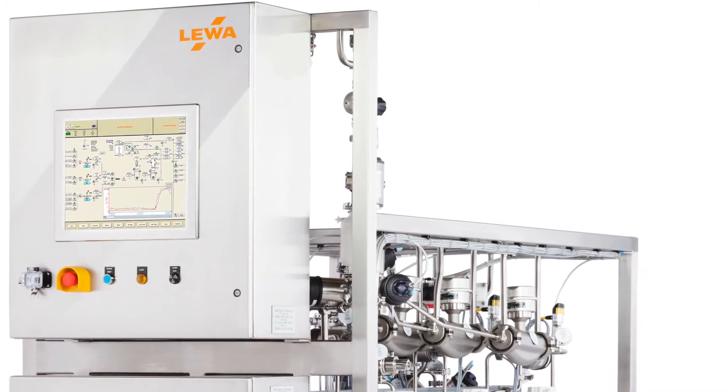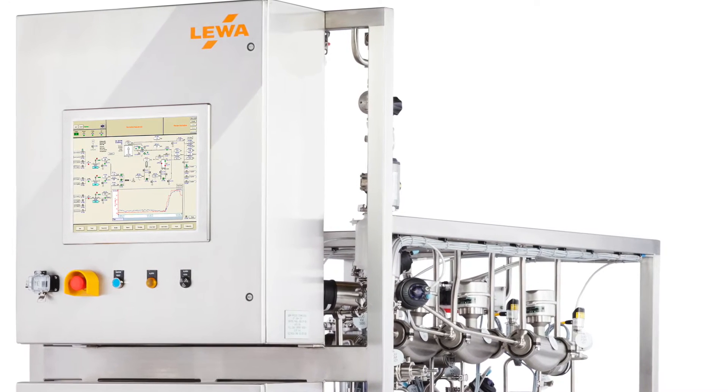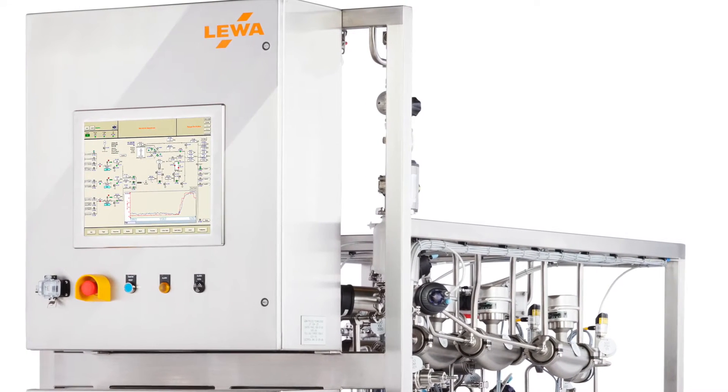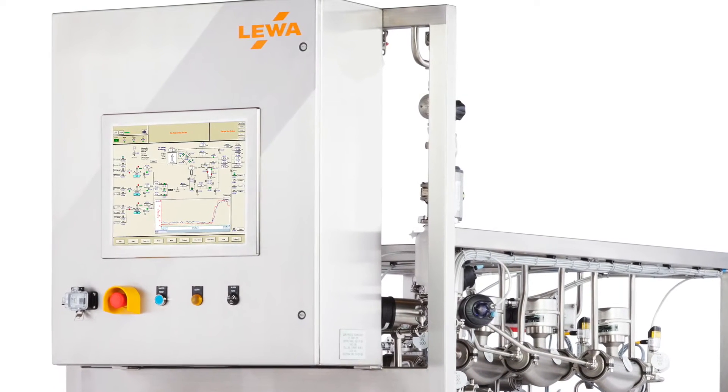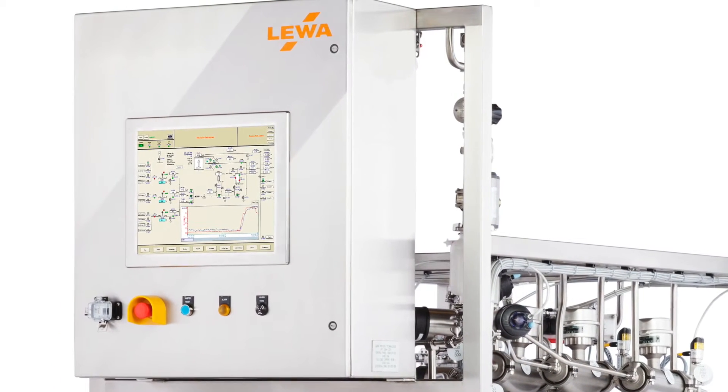The system includes a panel mounted PC HMI with a touch screen and manual control buttons and switches. Manual controls include emergency stop, master reset, and alarm indicators.